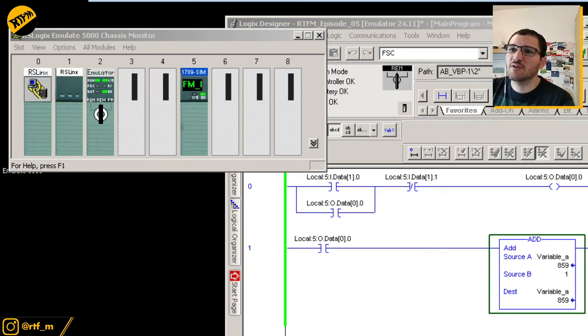Before we end this video, just a quick one, right, guys? The manual says on page 34, we've got a few indicators. So basically, you've got the LEDs. I'm just going to read that through to you guys. Basically, the run signal right here. So the LED, if it's off, the controller is in any mode but run mode, right? If it's solid green, the controller is in run mode. So that LED right here, right? I/O. So we've got our I/O LEDs.